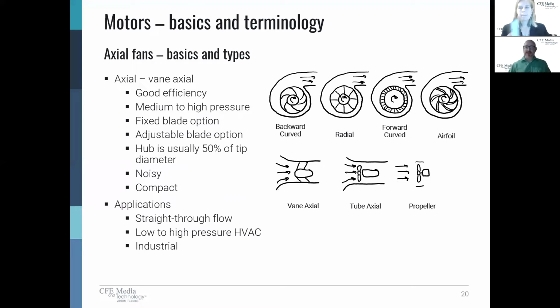The last type of axial fan we'll talk about is vane axial. Now, what's different about this is instead of having a propeller, like you would with a propeller fan and a tube axial, the vanes are actually running like the length of the motor shaft itself. Now, you'll know this by simply looking at it because the center hub of the motor is going to be like half the size of the opening. It takes up half of it, as opposed to the tube axial and propeller fans, where the propeller actually takes up most of the space. You just kind of see a small shaft in the center.